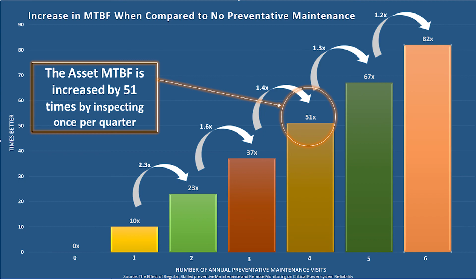The other thing that was done was the IEEE guys did a study where they looked at the cost of replacing versus repairing with and without a condition-based program in place. Essentially, if the outside of this spider web is the full cost to acquire an asset new, right? So if you look at the transformer thing, it's the outside right-hand corner there. If you have no condition-based program in place, it's going to cost you probably about 55 to 60% of the cost of that asset to institute a repair when it does fail. Versus if you have a condition-based program in place, it's probably about 25 to 30%. Right? Because why? You catch the problem earlier in the PF curve before that cost gets out of hand and you've caused secondary and tertiary damage to other components versus the one that had the initial issue. So it's the same with all those assets, and I think the average was like about a 66% decrease in your cost if you institute a condition-based program.